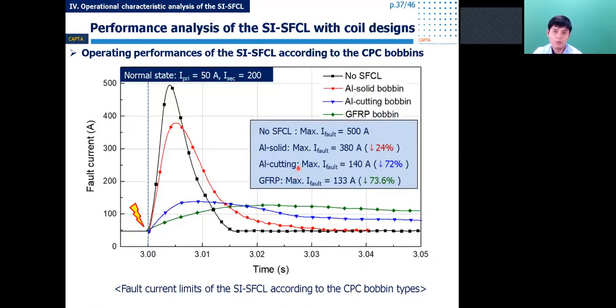Next is the performance analysis of the SI-SFCL with different coil designs. Firstly, the primary coil with a different bobbin design. The fault limit performance with 3 kinds of bobbin is shown in this graph. Using the GFRP bobbin and the aluminum cutting bobbin, you can see the SI-SFCL already achieved the design target. However, the GFRP bobbin could reduce the current rising di/dt better than the aluminum cutting bobbin. So it can increase the fault limitation time compared with the aluminum bobbin.